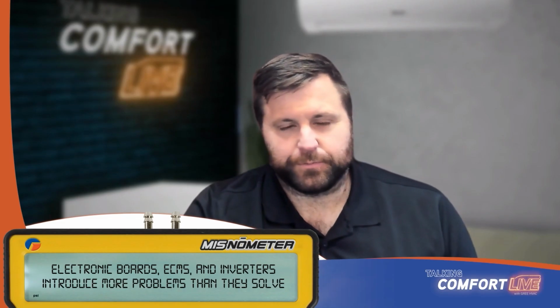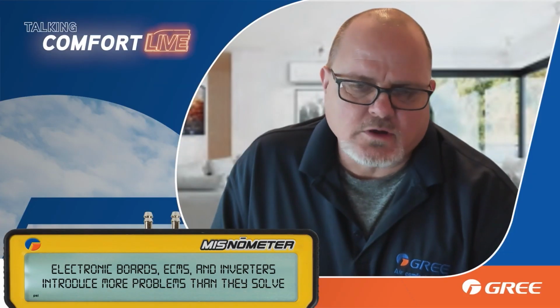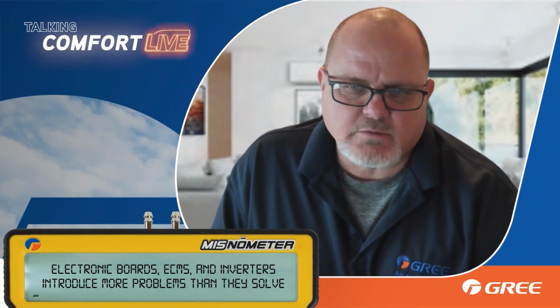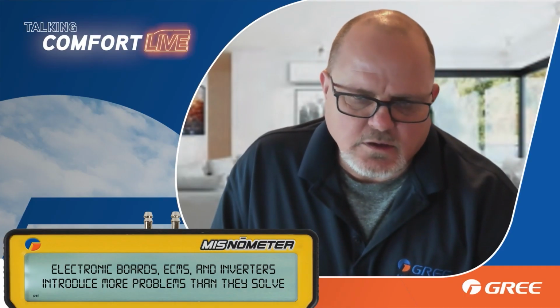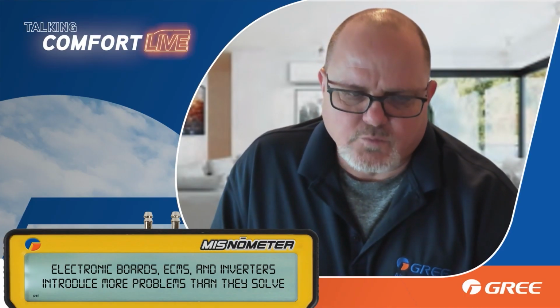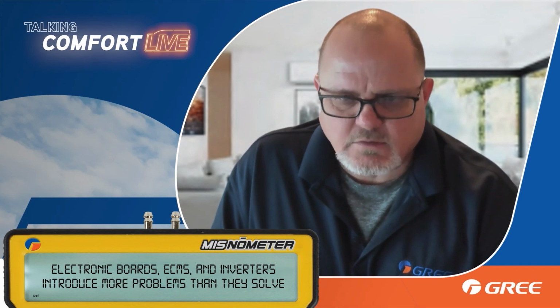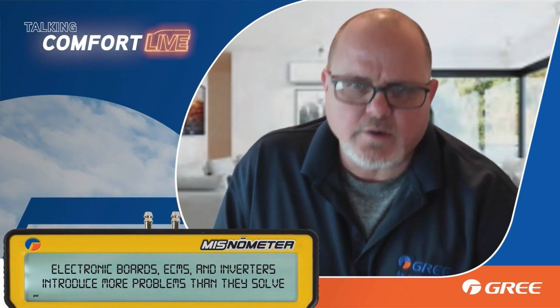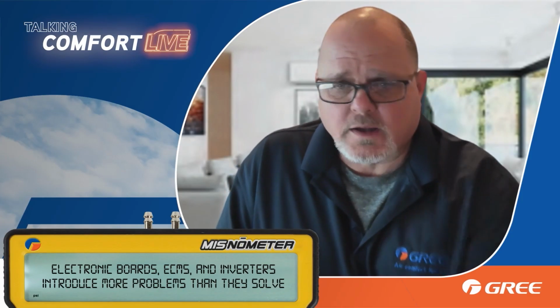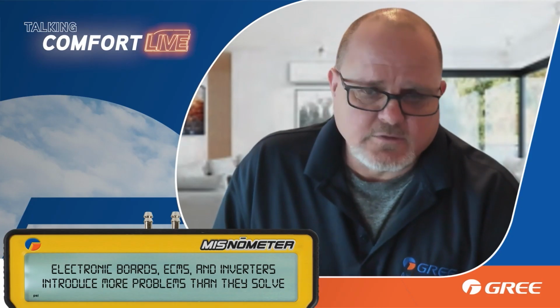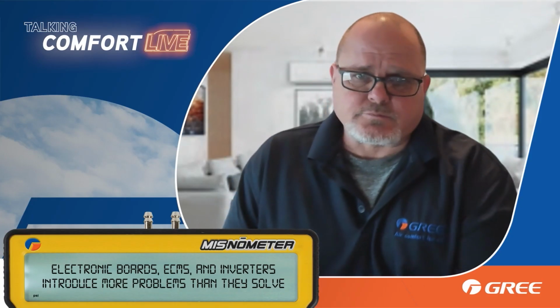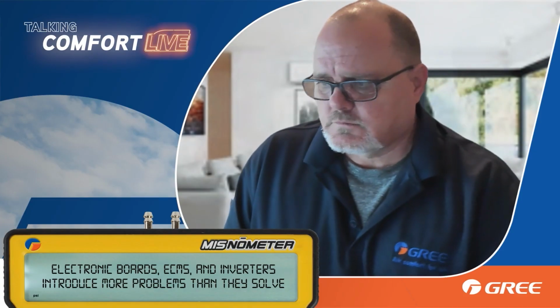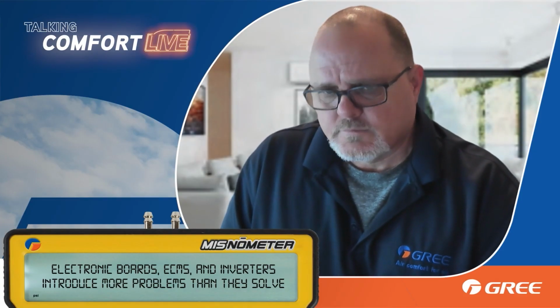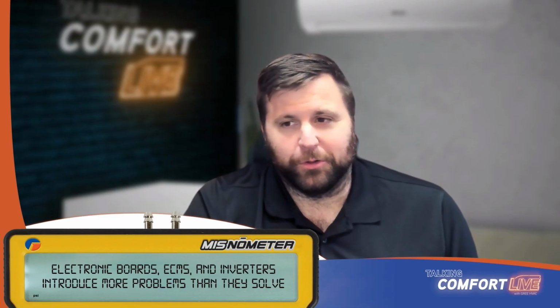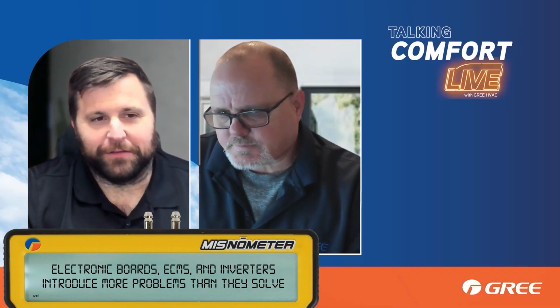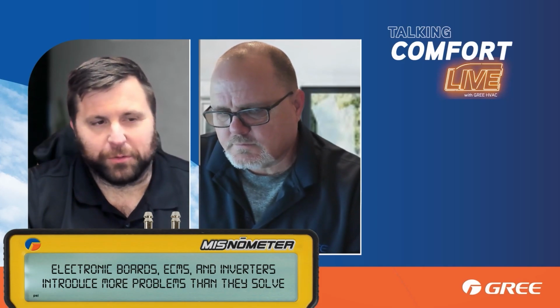But even the low pressure switches in today's equipment designs are more for lost charge. Unless that thing is almost completely out of refrigerant, that low pressure switch isn't doing any good. So you can have a system really low on refrigerant and still consistently overheat that compressor to the point of a compressor burnout, or like you said, the overload goes permanently stuck open. Right. Speaking of overloads, our overloads are externally mounted. So if the overload were to trip over and over again and finally go out, you can replace it. That's just one of those little design things that became recognized pretty quickly.